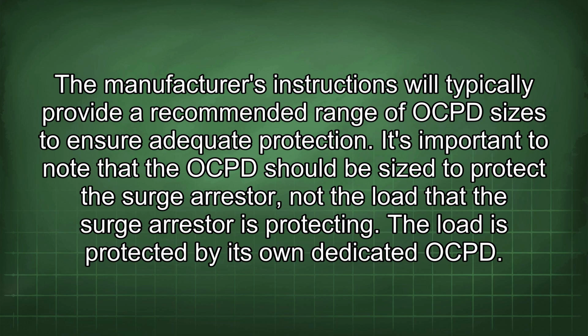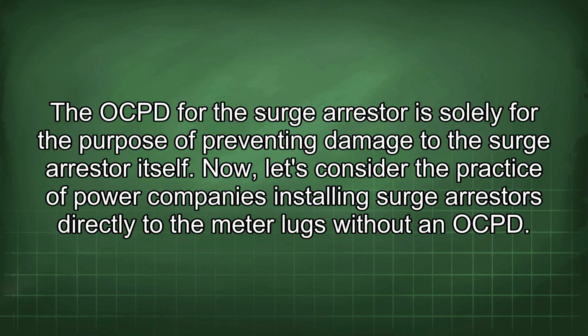It's important to note that the OCPD should be sized to protect the surge arrestor, not the load that the surge arrestor is protecting. The load is protected by its own dedicated OCPD. The OCPD for the surge arrestor is solely for the purpose of preventing damage to the surge arrestor itself.